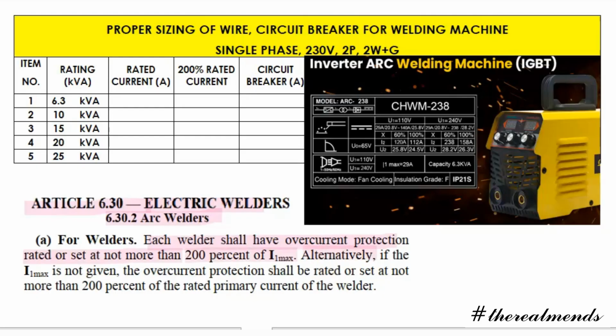So, alternatively, if the Imax is not given, the overcurrent protection shall be rated or set not more than 200% of the rated primary current of the welder. So means to say that yung Imax sa nameplate, so for this we have Imax of 29 amperes. So let's input this dun sa ating table. And then after i-input natin sa ating table, so ito na yun, rated current in terms of ampere.